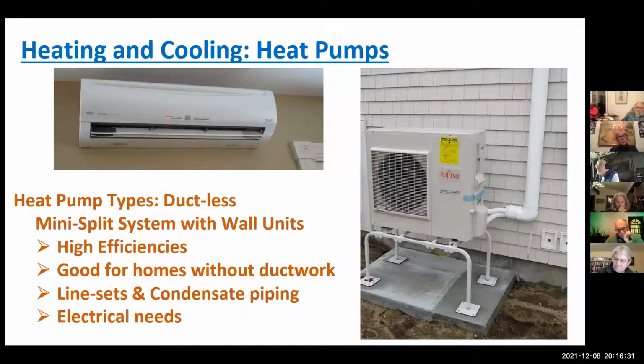Now, of course, you have to drill a hole in your wall to get to that. It has to have the line sets - the refrigerant lines that bring refrigerant to the unit and take it back to the condensing unit outside. It also needs electricity and condensate drainage, for that water from the humidity in our house. Where's it going? We sure don't want it running down the wall - we want it outside, somewhere it won't cause problems. So you just see that nice clean unit on the wall, but there are lines coming to it and leaving from it that we have to hide.